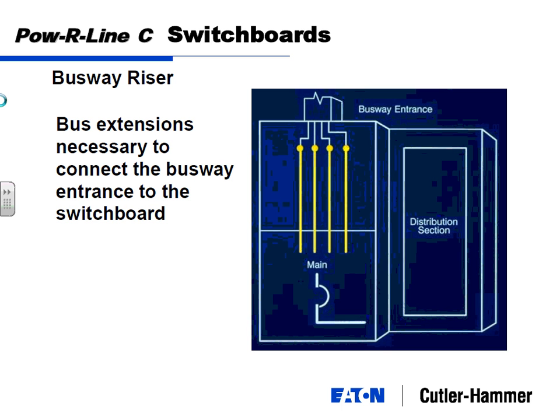There's different building blocks and stuff. And one more thing I wanted to mention on switchboards. We talked about cables this whole time, and I don't think you've talked about busway yet, probably. Next time. Busway is instead of cables feeding your switchboard. Say you've got one main switchboard, a 4,000 amp main switchboard, and you're feeding two 2,000 amp distribution switchboards.